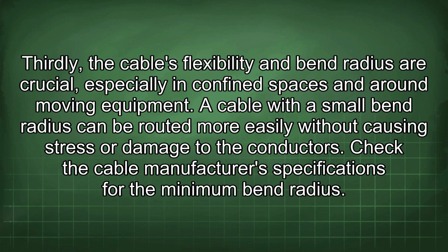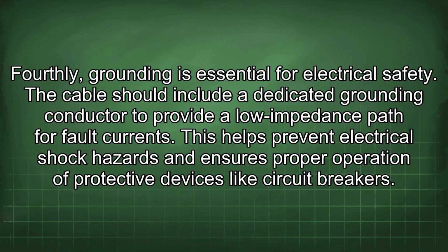A cable with a small bend radius can be routed more easily without causing stress or damage to the conductors. Check the cable manufacturer's specifications for the minimum bend radius. Fourthly, grounding is essential for electrical safety. The cable should include a dedicated grounding conductor to provide a low impedance path for fault currents. This helps prevent electrical shock hazards and ensures proper operation of protective devices like circuit breakers.